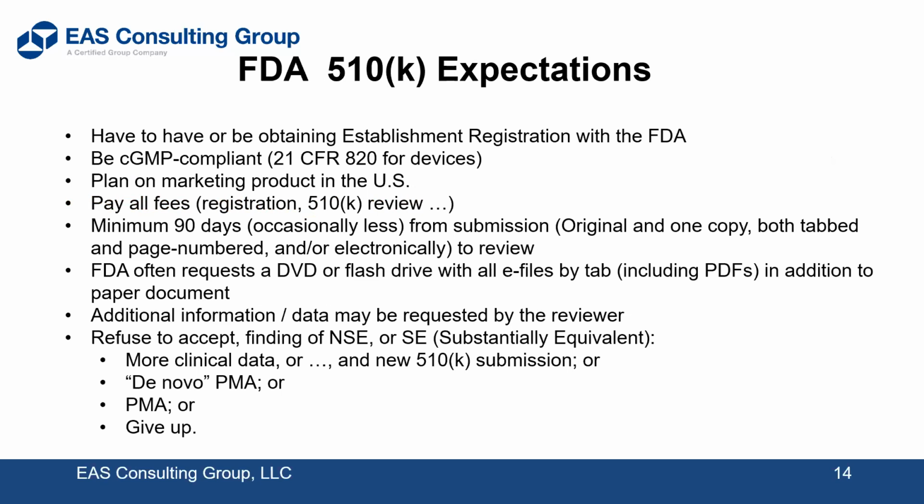They're expecting that when you build your product, it's going to be compliant to the GMPs, the current good manufacturing practices. So if you're familiar with the GMPs for devices, that's 820. You know that you usually will not pass an FDA inspection just by virtue of adhering to the written GMPs. You're expected to be current. You're expected to be where your industry is in general, in the middle of your industry.